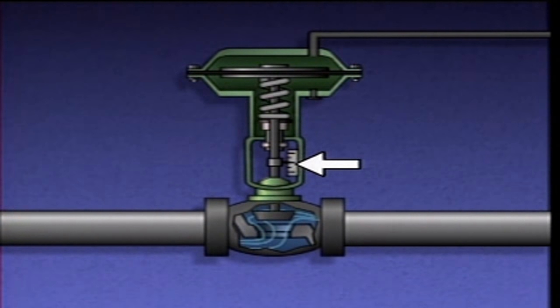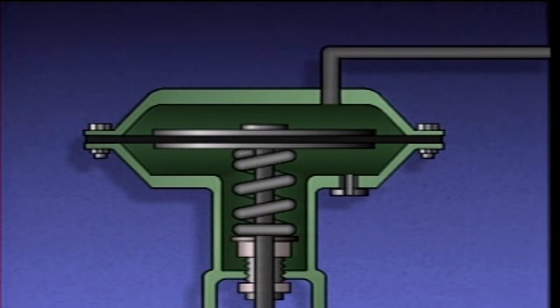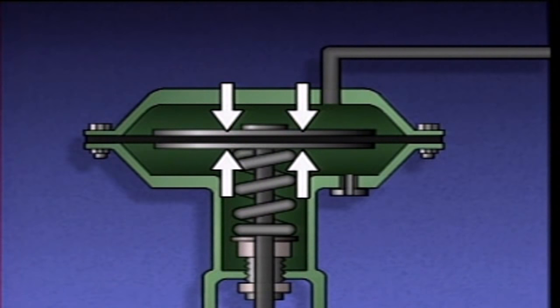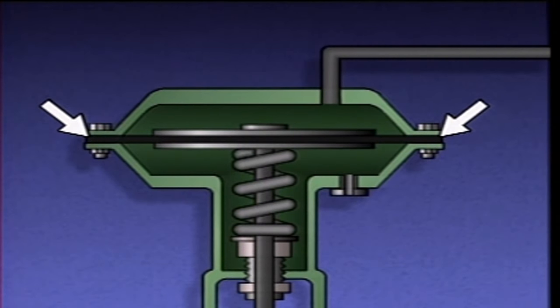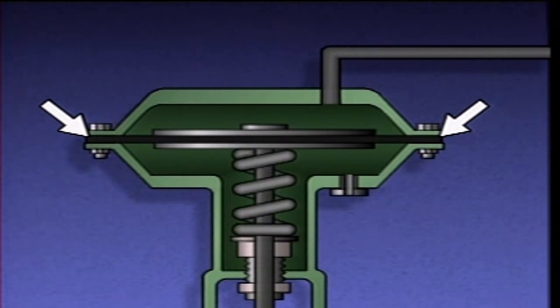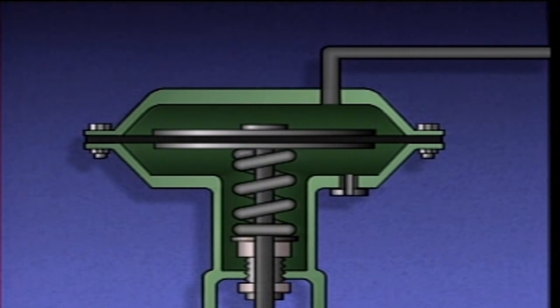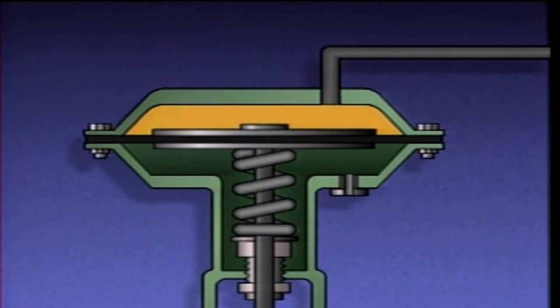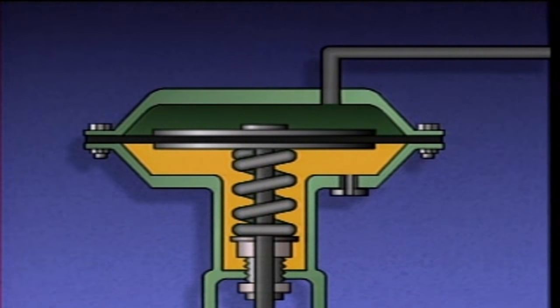The indicator shows the position of the valve. The center of the diaphragm is supported by metal plates, and the outer edge is sandwiched between the rims of the upper and lower halves of the casing to form an airtight seal. This arrangement divides the casing into an upper chamber and a lower chamber.